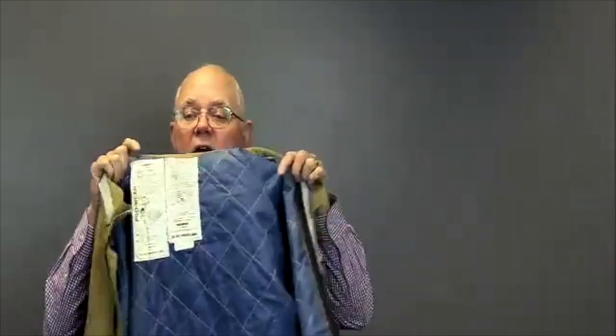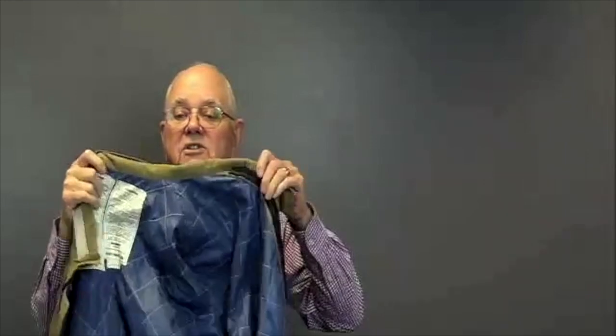And the same is true. The arc flash suit will also have a jacket with it as well. There's a label on the inside for me to check the ATPV rating. One thing when I put it on is I want to fasten all of the snaps and buttons or zippers or whatever it has. But I want to make sure that it also gives me adequate room for movement and visibility. If not, I'm not going to want to wear it.